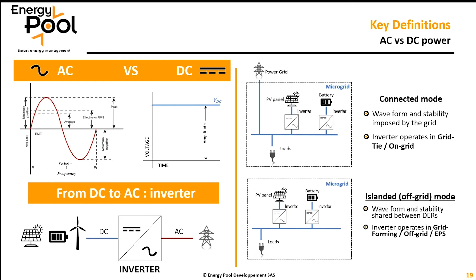Because of this, in an islanding microgrid, we need to define some operating rules, because we need to define who will create the waveform and who will be responsible for the stability, since it has to be shared between the distributed energy resources. That's what we did here for our example. We defined some operating rules: the thermal plant should operate with a minimum load ratio of 50%, except when one single genset is running. This is for a yield reason. The second one is that, to ensure the stability and the inertia, for the reasons that I exposed before, the genset will create the waveform of the voltage, so it should always cover 20% of the load.